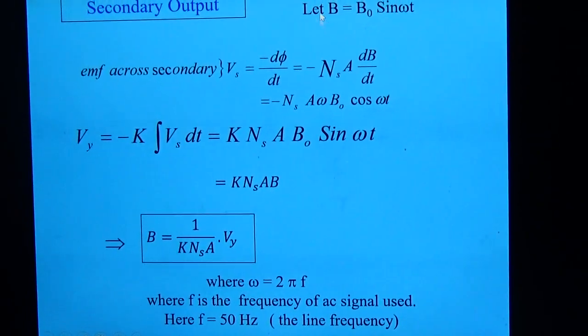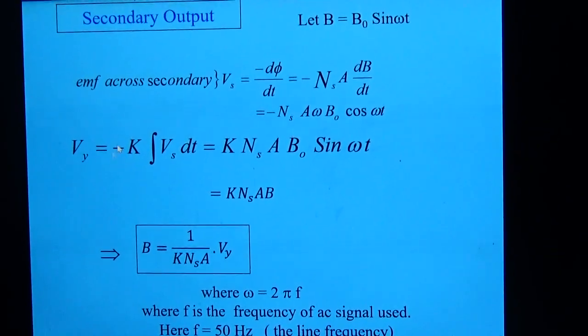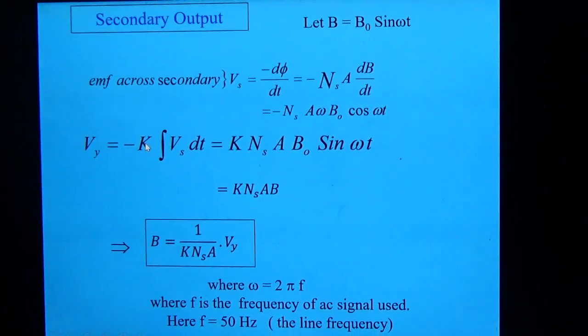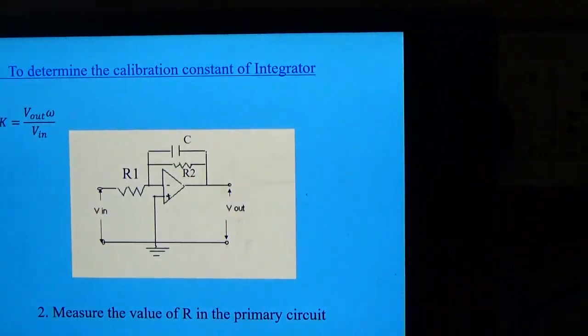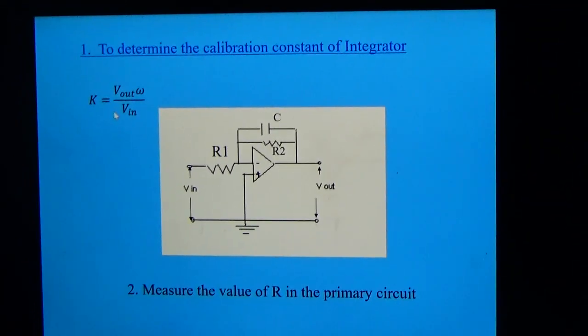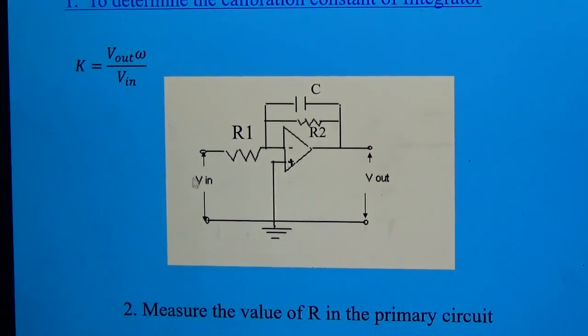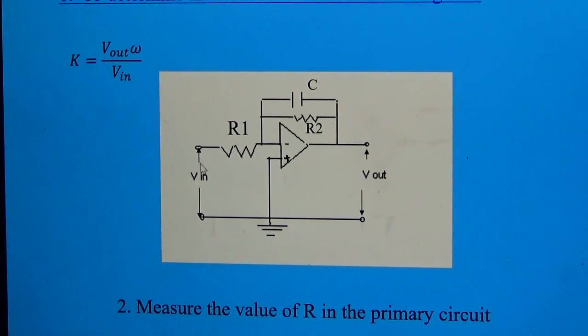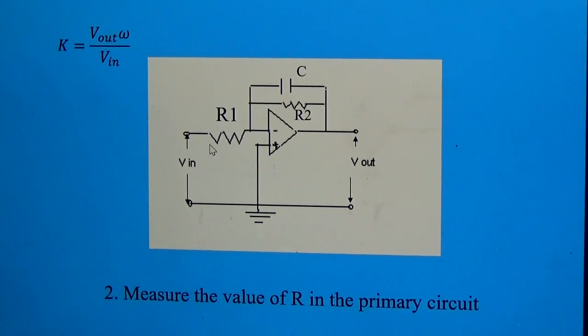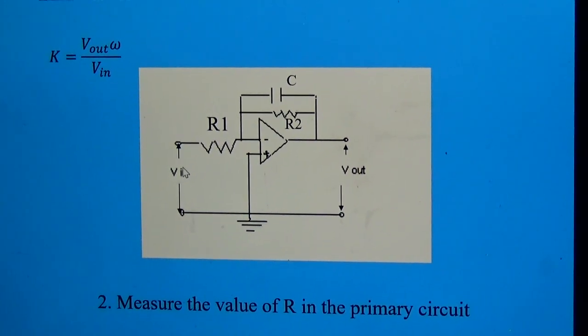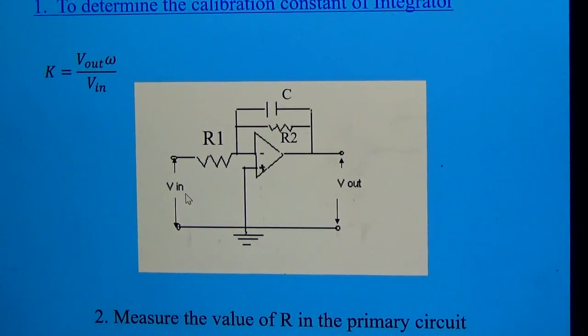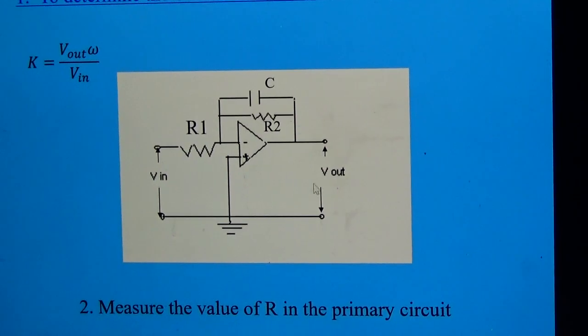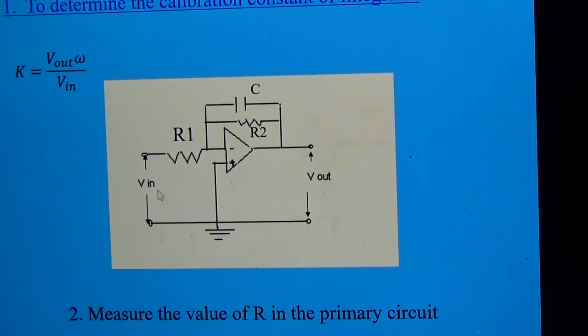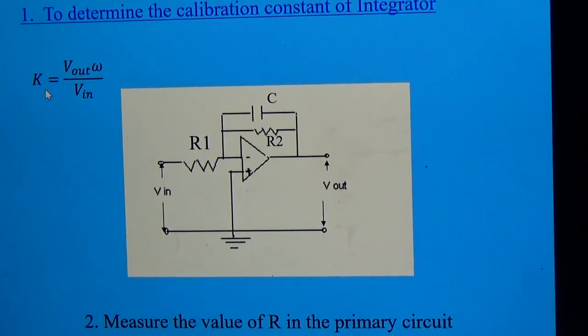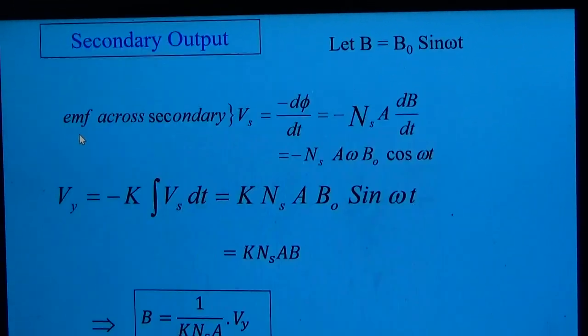So in order to measure the magnetic induction, we need to measure the integration constant. So which can be measured by changing the input. So what we do is we basically measure by changing the input to the integrator. That means by applying different magnetic fields, we can change the corresponding input to the integrator, and by measuring the output for different inputs, we can measure the calibration constant.